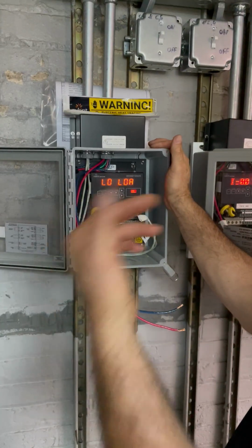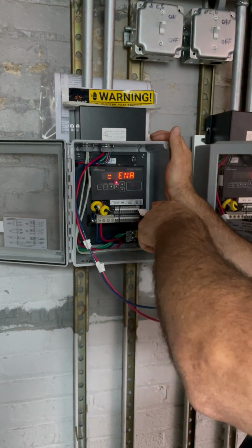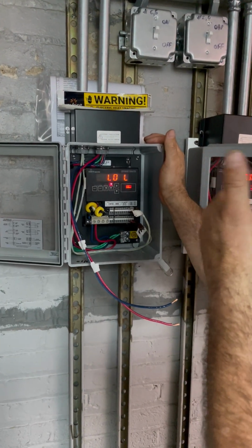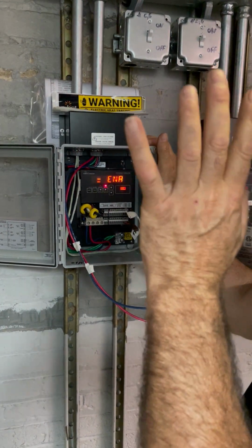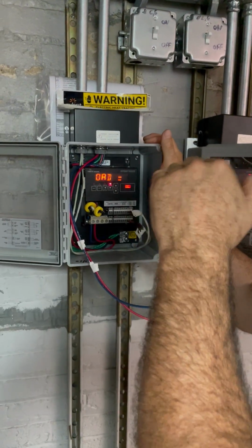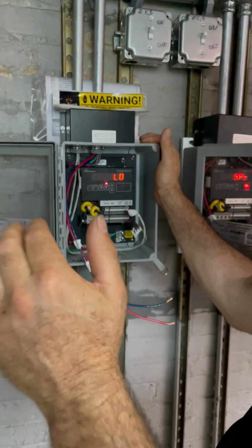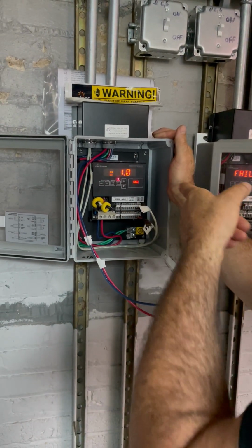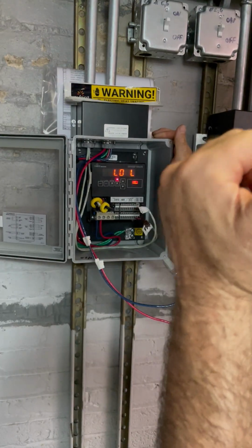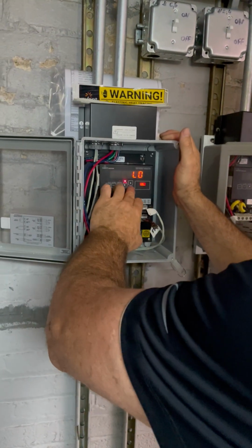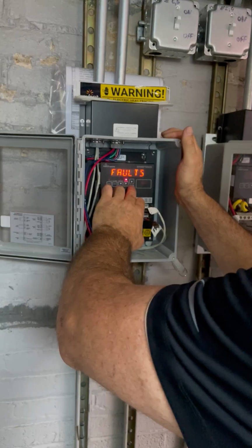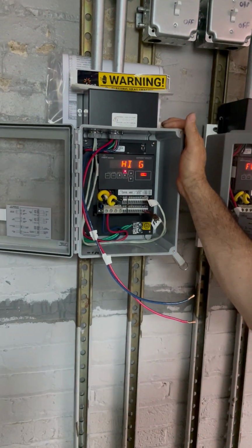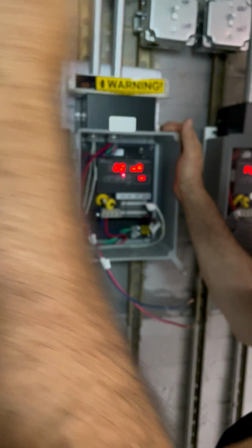Now, back to the flashing light. That's all you get for an alarm. So if you're not tied into the BMS, and somebody doesn't walk by here and see that and do something about it, nobody's going to know. All right, so we're going to enable a low load. The default is 1 amp. These are pretty short, so we may have to drop that a little bit. Will it make any sound or just? This is it. That's all you get. It's intended to be tied into something. These usually are mounted out to the BMS. Yeah.